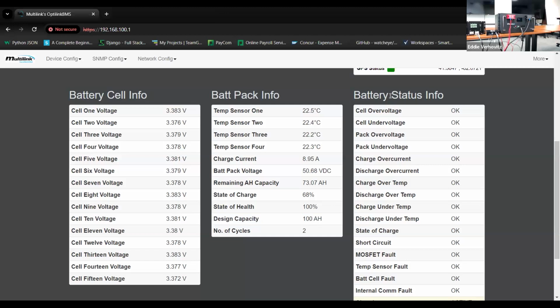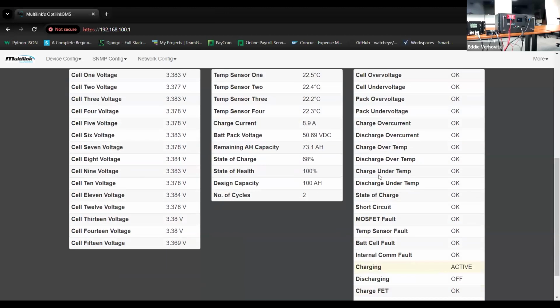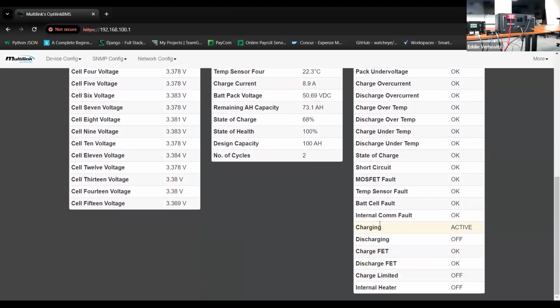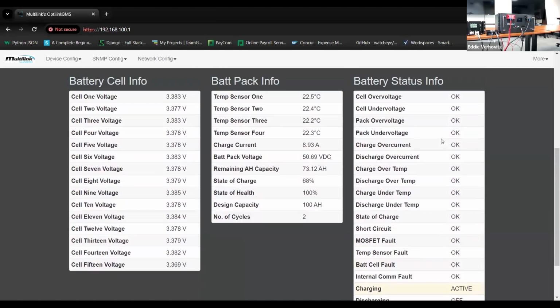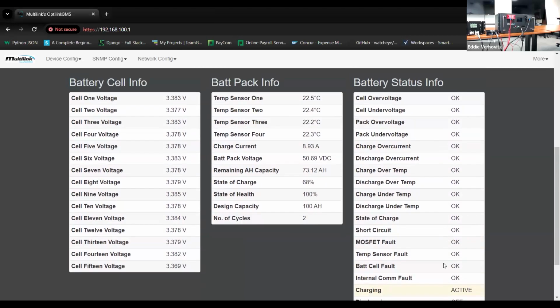In the rightmost column, our battery status info column, this is where our cell voltage, pack voltage, charge and discharge, alarm, and protection indicators are stored. So right now, anything labeled as OK currently does not have an active alarm or is not in a state of alarm condition or protection.